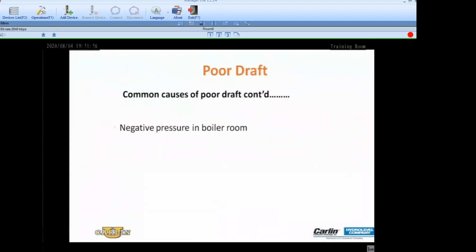Negative pressure boiler room. Again, more common than we sometimes understand. Technicians should be instructed that when they walk into a boiler room or a furnace room, and more important, a furnace room probably, close the door behind you. When you walk in, you're going to do a test. Close the door behind you. When that fan comes on in the unit, is it drawing air from the room? Do you have that many leaks in your ductwork that you're creating negative pressure in the room?